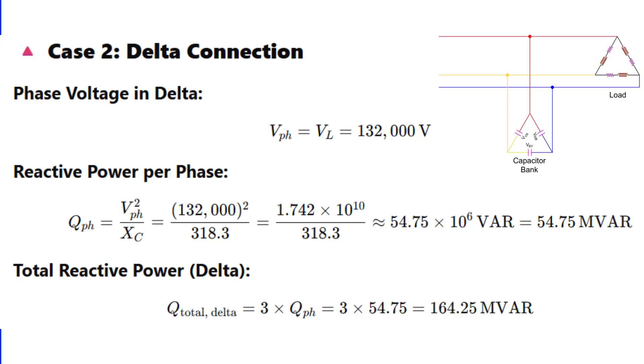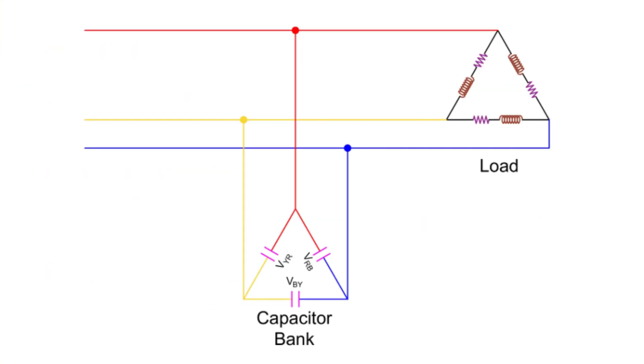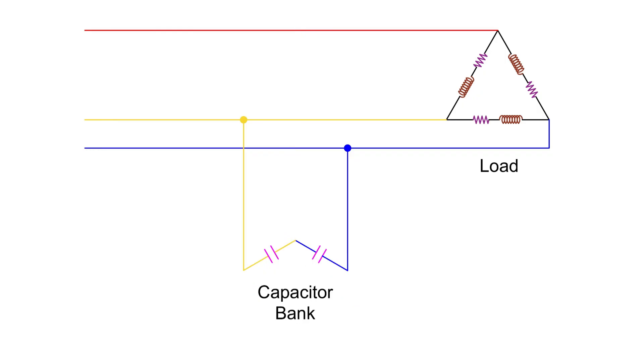And it doesn't end there. In delta, if one capacitor unit fails or is removed for maintenance, the other two still form a closed path and continue to supply reactive power. But in star, the loss of one leg makes the whole bank unbalanced and less effective. Also, delta doesn't require a neutral connection, which is often not available in high voltage substations. That makes installation simpler.